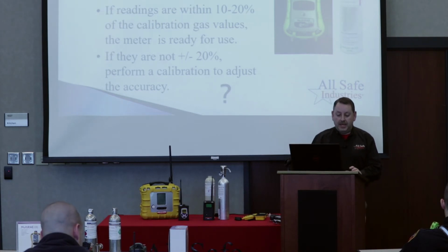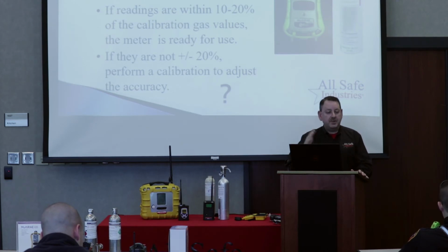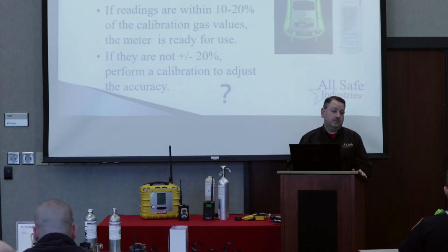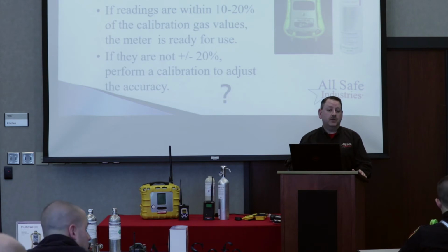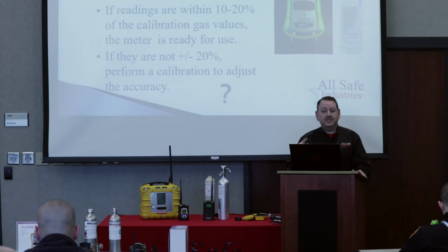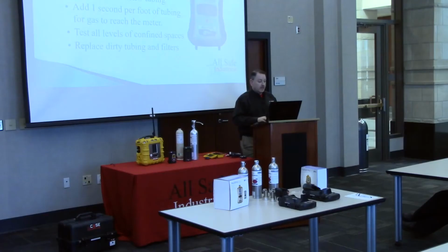Yep. All right. And again, if you're doing the bump check and your numbers are off by 20%, well, that just means it's not reading super accurately. You can make the decision if you're going to use it or not. I'd probably want to recalibrate it if it was off by 20%. But if I'm trying to get to 50 ppm CO and I'm at 48, that's good. You know that the meter will detect CO. The most dangerous thing you're watching for is when you put gas on a meter and the sensor just sits at 0. Okay? That's what we're trying to catch when we run a bump check.